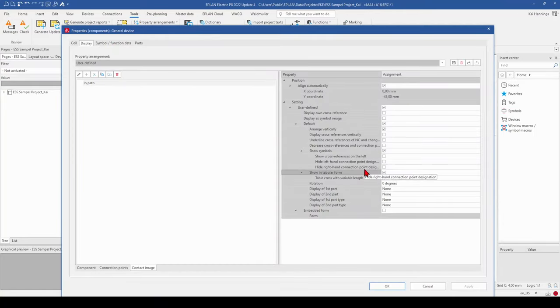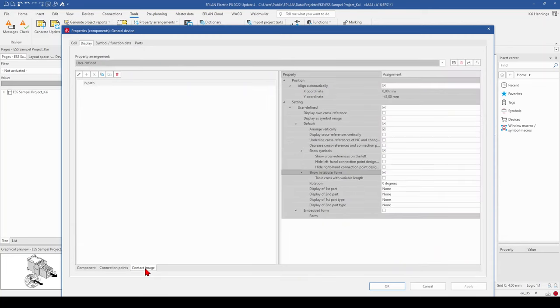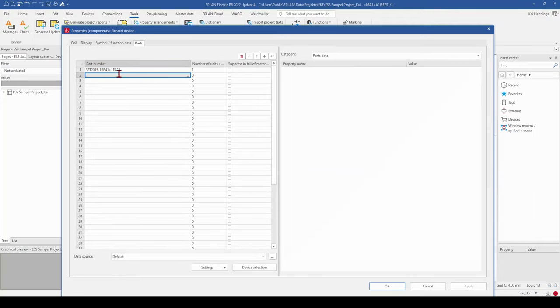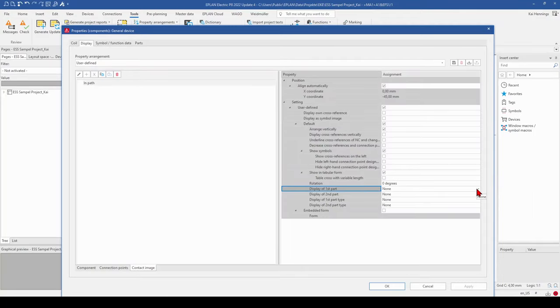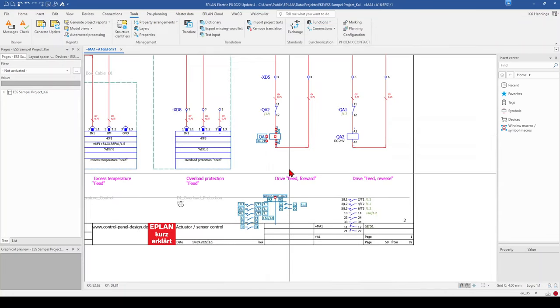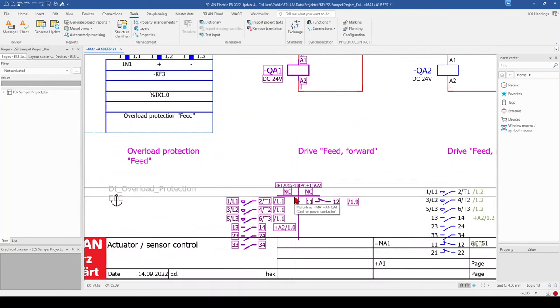Another question I get regularly is how to display the part number. We have here the part number for our contactor. When we go back to Display and to the tab Contact Image, we can also set Display of First Part. You can also show Display of Second Part — for example, if you have a contactor with auxiliary contacts as a second part, you can show both. When we click on First Part, On Top, and click OK, you can see that EPLAN automatically shows the part number above the contact image.